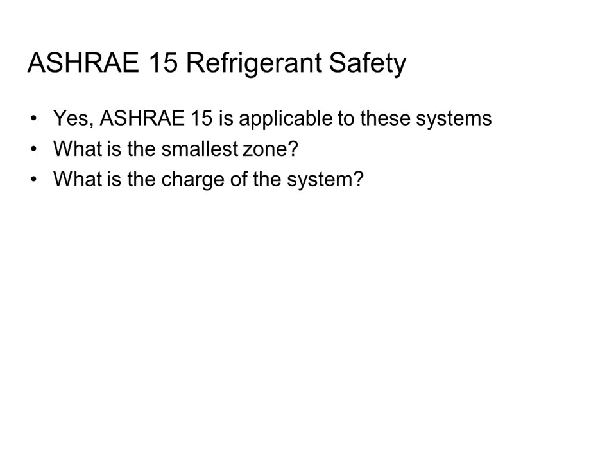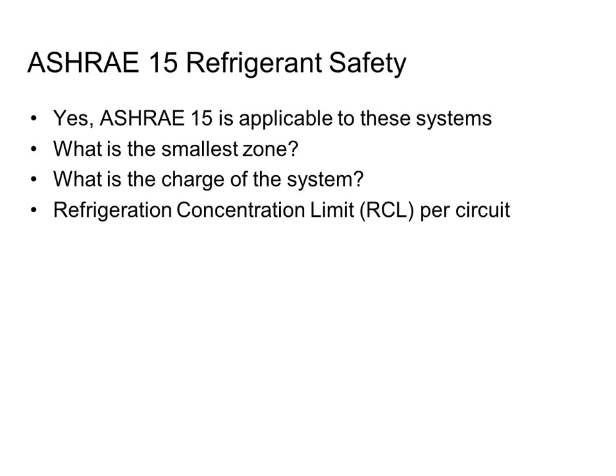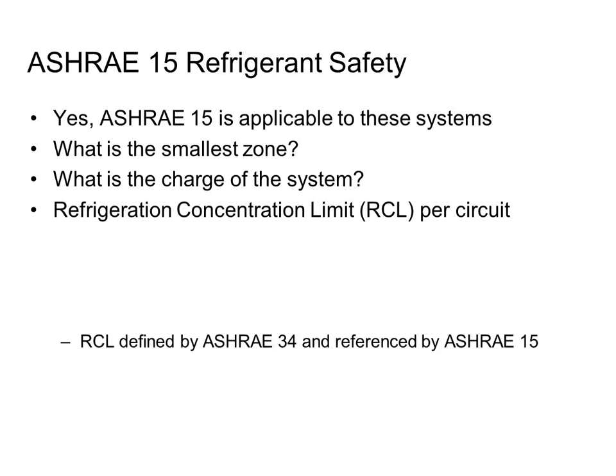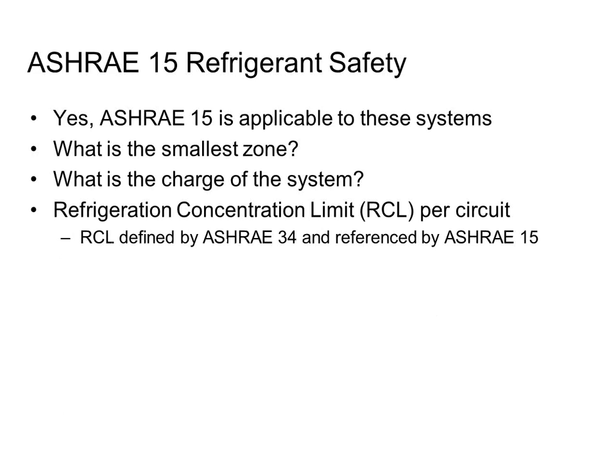And by the way, it's not how many pounds of refrigerant were shipped in the condensing unit. It's how many pounds are in my system when it's installed and charged. Once I add 300 feet of pipe, that number is going to be more than whatever came in the condensing unit. Then I have to look up the refrigerant concentration limit. Where do you get that? Well, in the city of Chicago, they publish their own limit. For ASHRAE 15, they refer you to another ASHRAE standard, because that's what we do at ASHRAE to get you to buy more standards. So you look at ASHRAE Standard 34 to find out what the RCL is, the maximum amount of refrigerant I can have on each individual circuit of refrigeration.